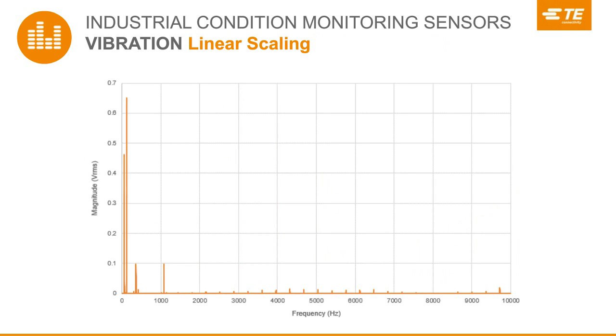On the previous slides, we showed the spectral plots as log magnitude versus log frequency. Why? Well, here's what we see if we use linear scales for both X and Y. The lower frequency signals are kind of huddled up towards the left-hand side. The presence of the high frequency harmonics for the machine in bad condition can barely be seen. These components can be 40 dB down, or a factor of 100 less than the running speed component. Logarithmic scaling lets us see the details that would otherwise be very difficult to resolve. This also shows why we need a high dynamic range and a very low noise floor from an accelerometer for condition monitoring.